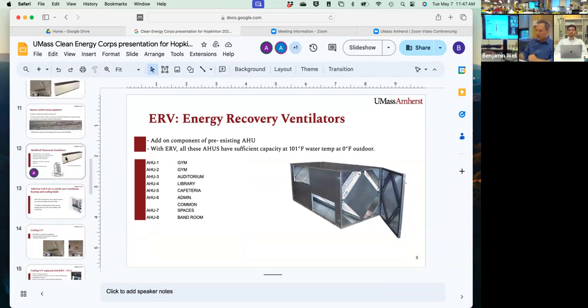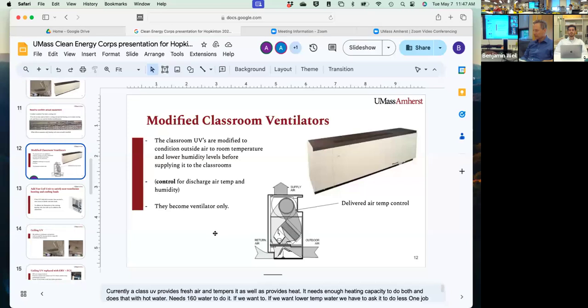So for the classrooms with unit ventilators that go through the wall, these are not problematic pieces of equipment. It's just expensive and complicated to try to add an ERV that's going to duct to the rooms and all that stuff. So for these simple systems, we basically made the judgment that you pay for the ventilation. You're not going to do any heat recovery on ventilation for those classrooms, just because we're trying to keep the upfront cost low. And remember, your energy, you're operating at 500% efficient. So that heat recovery during occupied hours only, it's not huge.